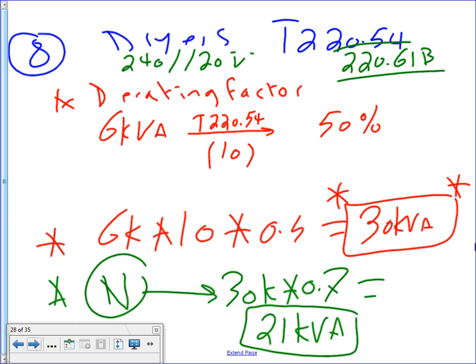Why do we count it under 220.61(B)? Because when you wire them, you send a neutral there. The way they manufacture the dryers, the heating element in an electric dryer runs at 240 because it's a big load. And the motors, remember the dryer has a motor that rotates and flips things around as you dry them. That runs at 120, and some controls too run at 120.